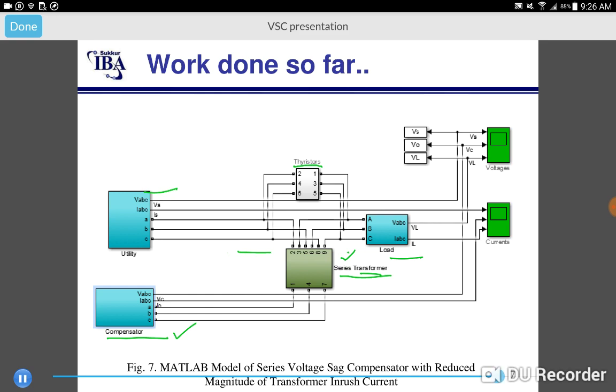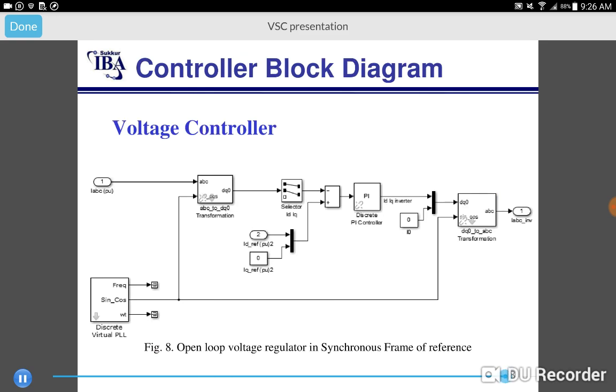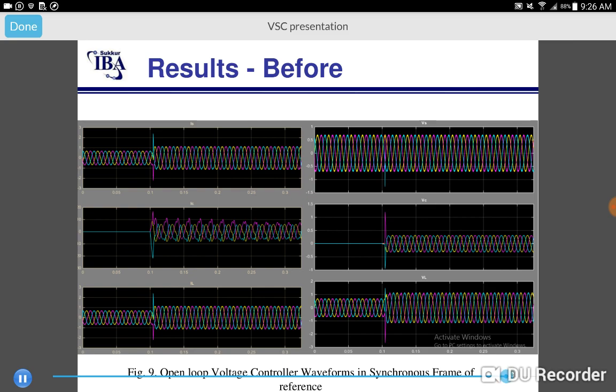But when the compensator is on, the series transformer gets energized and an inrush current is generated in the transformer windings, as discussed in this figure. The amount of inrush current sometimes goes thrice the value of nominal current in the transformer.